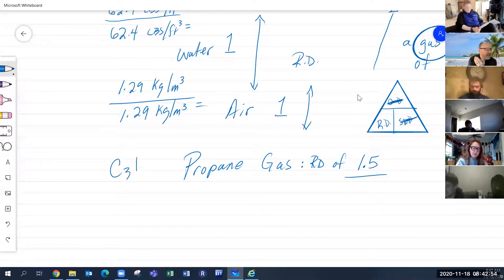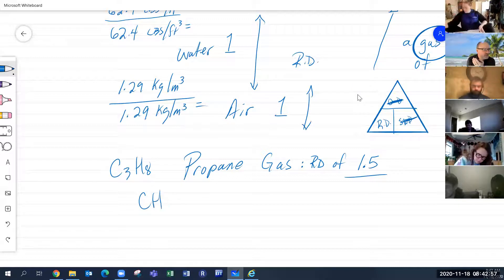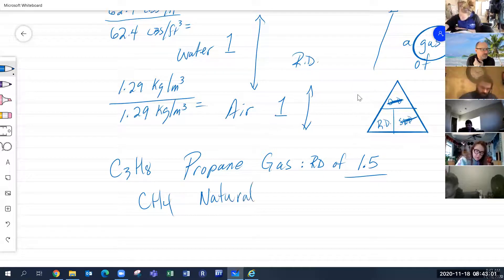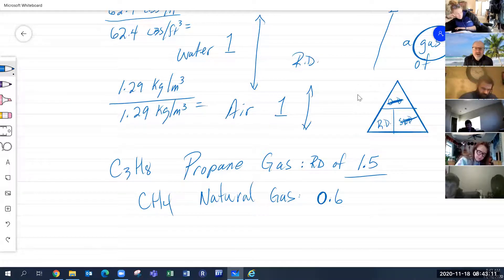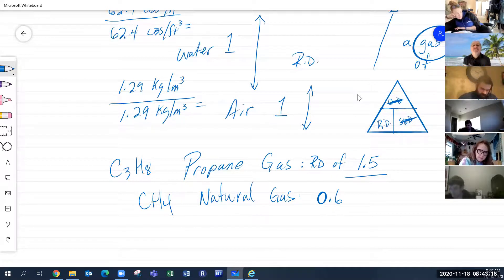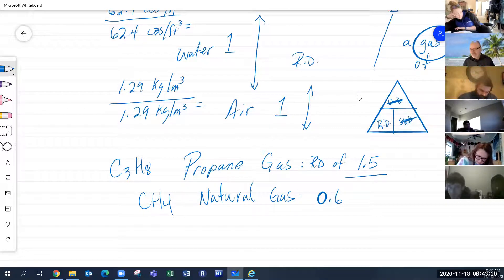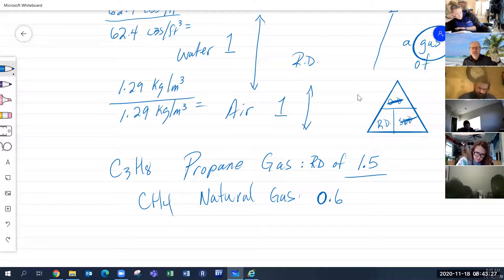C3H8 is propane, and CH4 is methane or natural gas. Natural gas has a relative density of 0.6 — it's lighter than air. So if natural gas is released into a room, it rises to the ceiling.